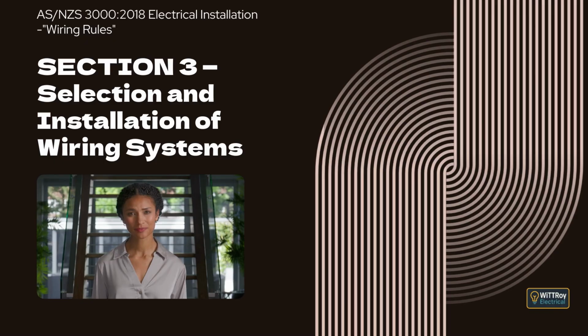Clause 3.9.10, Limitation of circulating and eddy currents. This clause introduces requirements to limit heating caused by induced currents. Clause 3.9.10.1, General. This clause states that precautions must be taken to limit circulating and eddy currents. Clause 3.9.10.2, Cables for AC circuits, electromagnetic effects. This clause explains that single-core AC cables must be arranged so that all phase conductors and the neutral are contained together, especially in ferrous enclosures, to prevent excessive heating.